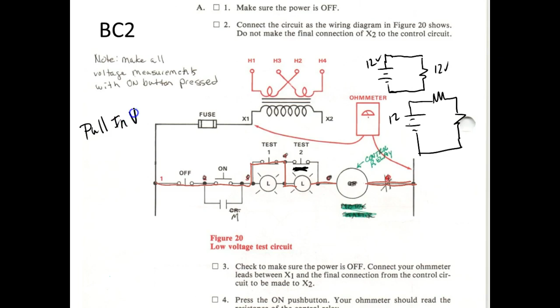Is it going to stay in or is it going to drop out? Well, what we're going to find out, relays have two different voltages that they specify. They specify what we call the pull-in voltage. That's how much voltage you've got to put across the coil for it to generate a magnetic field strong enough for that plunger to come up. And the pull-in voltage is going to be quite high. It's going to be high because you've got that big old gap you've got to fill in, right? You understand? On your solenoid. Everybody understand that?